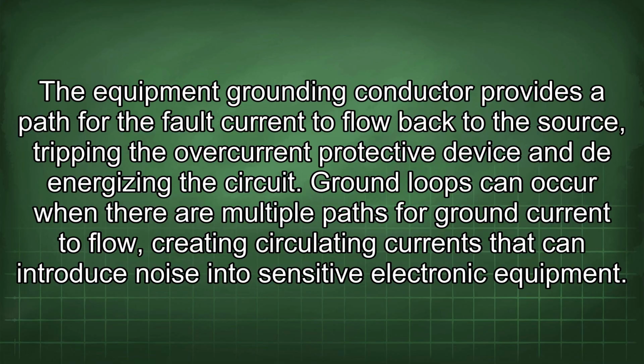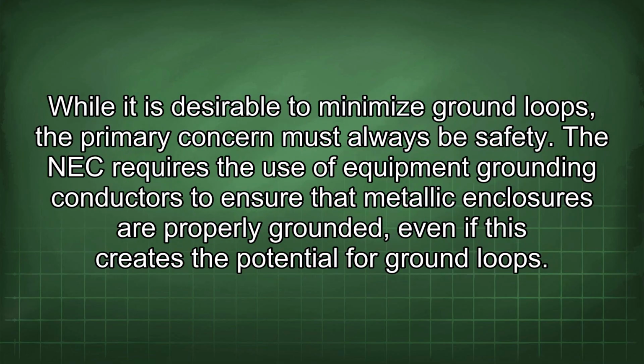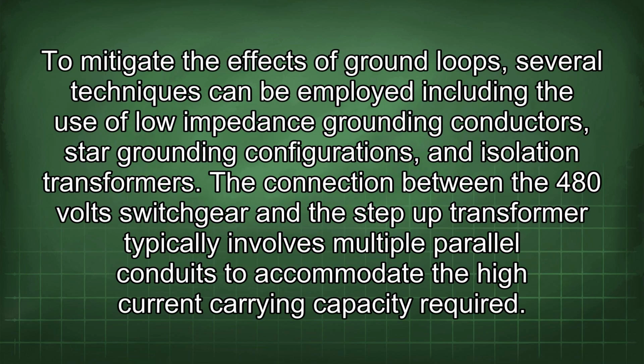Ground loops can occur when there are multiple paths for ground current to flow, creating circulating currents that can introduce noise into sensitive electronic equipment. While it is desirable to minimize ground loops, the primary concern must always be safety. The NEC requires the use of equipment grounding conductors to ensure that metallic enclosures are properly grounded, even if this creates the potential for ground loops. To mitigate the effects of ground loops, several techniques can be employed, including the use of low-impedance grounding conductors, star grounding configurations, and isolation transformers.